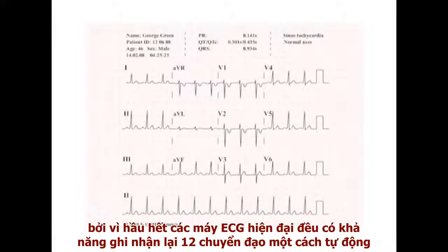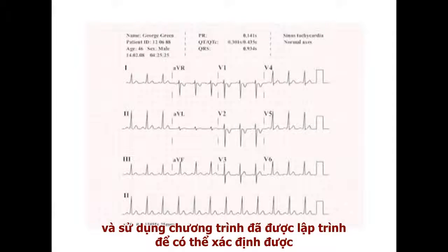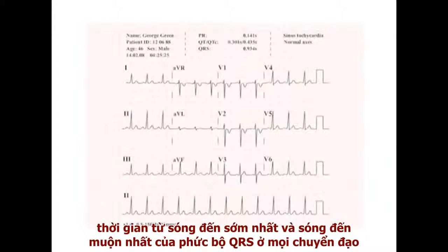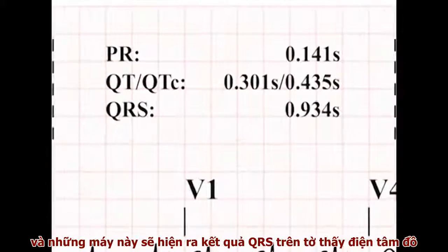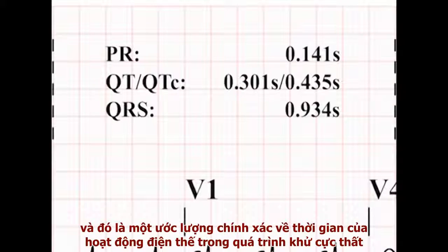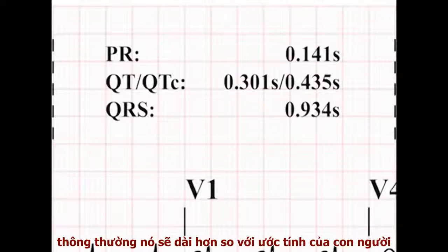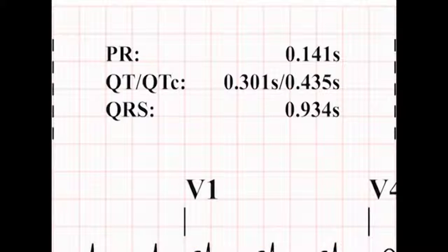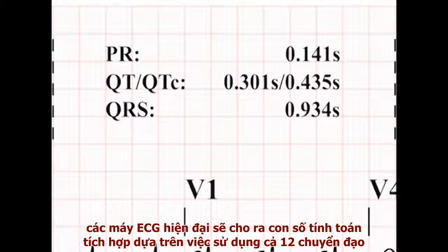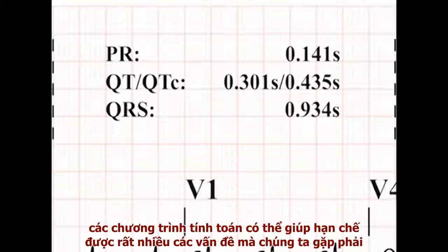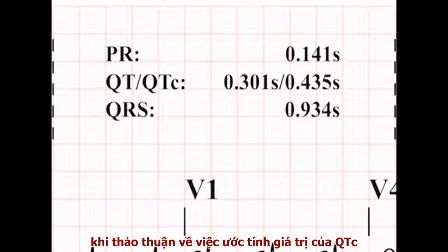Most modern digital ECG machines are capable of recording all 12 leads simultaneously and use computer programmes to identify the times of the earliest and latest deflections of the QRS complexes in all leads, then report this integrated QRS duration on the printout. This tends to represent an accurate estimate of the duration of all ventricular depolarisation events, and will always tend to be longer than the human estimate. The same problems exist for the PR interval and QT interval, and modern machines present an integrated value calculated using all 12 leads.